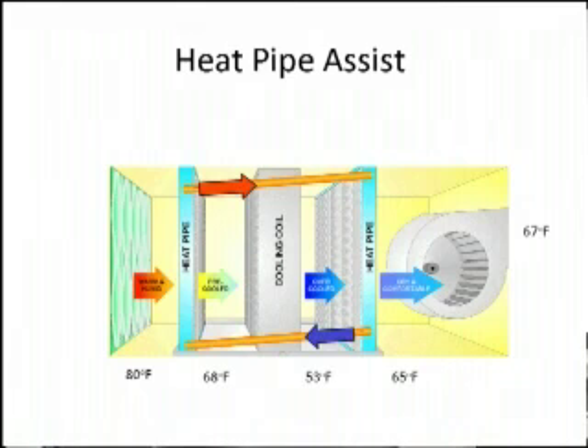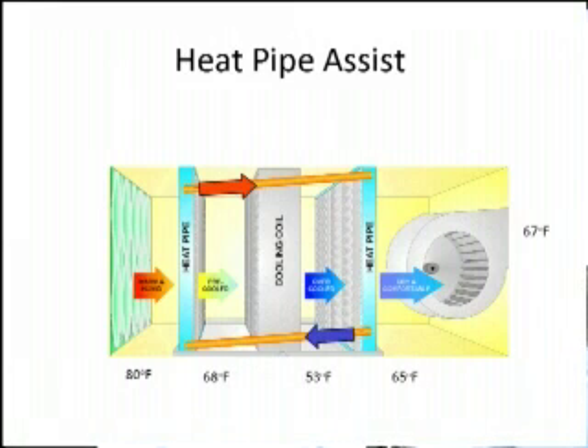So here we've got some temperatures — these are real temperatures from a real example. We're bringing in air at 80 degrees, and that's cooled down to 68 degrees before it hits the coil. So we're using a lot less refrigeration capacity, because we're only going from 68 to 53 instead of 80 to 53 like before.